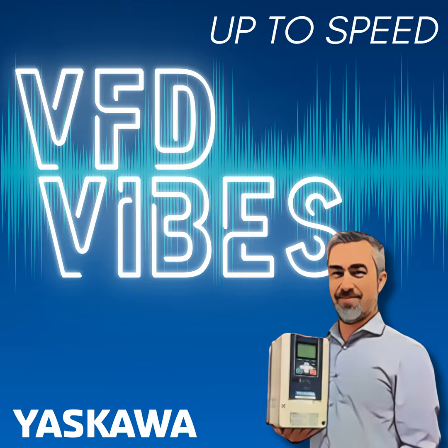If there's any imbalance, we start to see a 120 hertz component on the DC bus. And the more imbalance we have, the bigger a part of the ripple that 120 hertz becomes. The amplification of it. Right. And the worst case is single phase, where it's all 120 hertz ripple. Yes. Right.